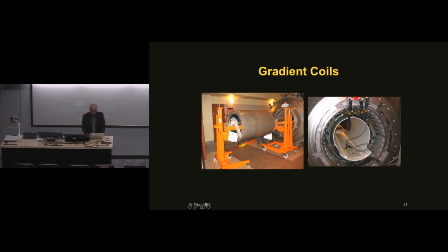They're loaded inside the bore of the magnet and driven by these huge big cables. Those are resistive. You've got massive amplifiers running at rail voltages over 1 kilovolt, dumping huge currents down there. They get hot, and now the latest systems have lots of plumbing in them to try and water cool them. That was, for a long time, a big technical limitation, and engineering innovations pushed those to enable faster and faster scanning, which was for many years a big bottleneck.